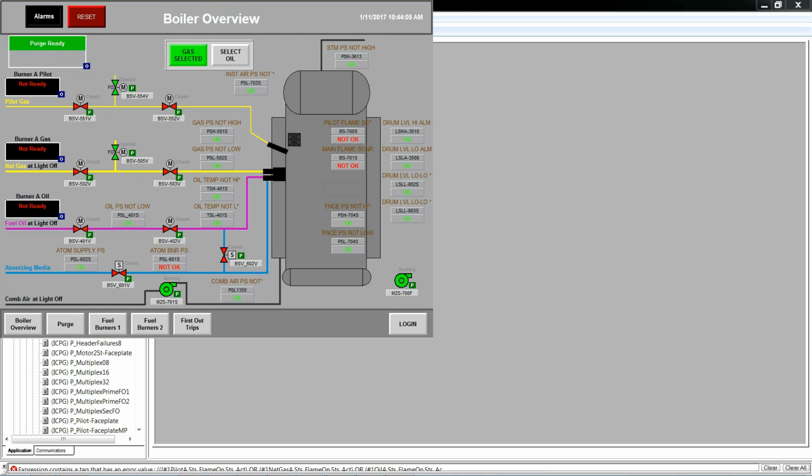Well, okay. So now we're getting into kind of the interpretation and semantics of NFPA. Currently, our interpretation of that split systems is that you would require a logics for the BMS or the safety side, and then you would need a logics for the process or the combustion side. So that's how we design things.